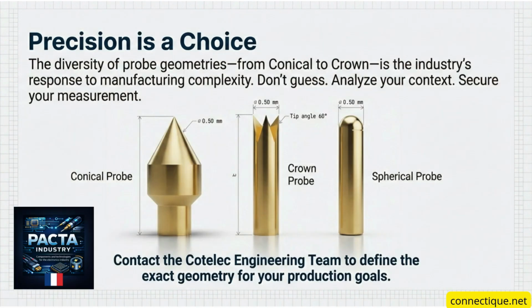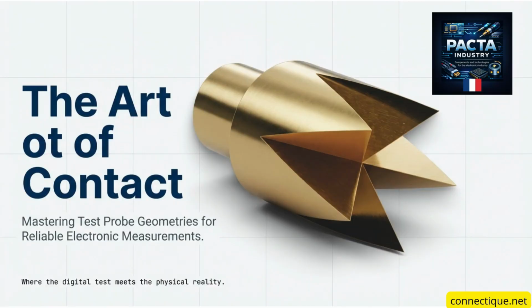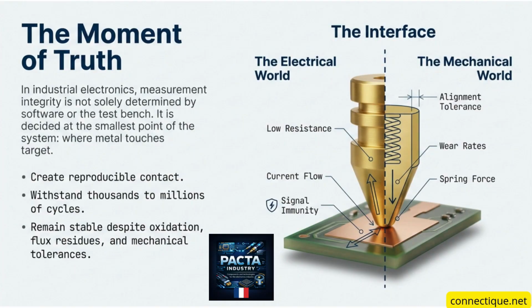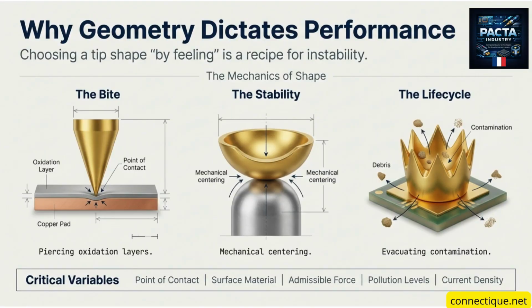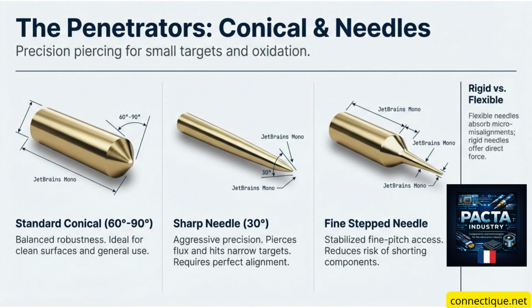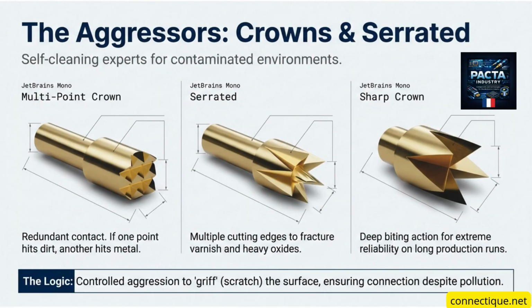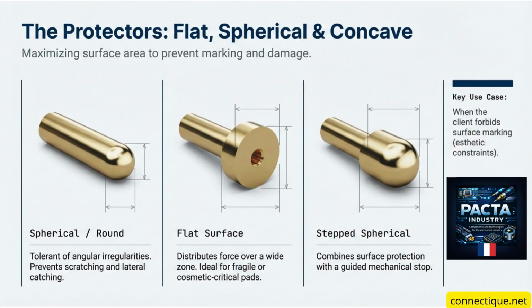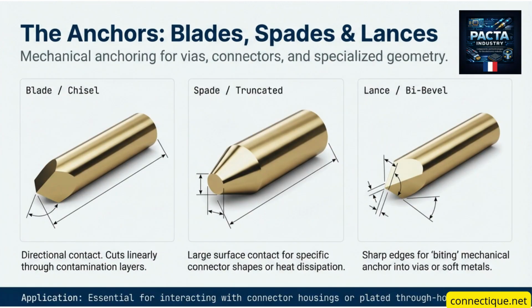We live in a digital world, right? We think of electronics as code, software, invisible signals. But at the foundational level, reliability is about geometry. It's about a shape. It's about the tangible world. It is. It's about choosing the right physical form to bridge the gap between the mechanical chaos of the world, the dirt, the vibration, the misalignment, and the electrical perfection we demand. It's the 30-degree cone versus the 120-degree cone. It's the decision to scratch and to glide. And realizing that a simple metal stick is actually a highly engineered, self-cleaning, stress-managing organ of the test system.